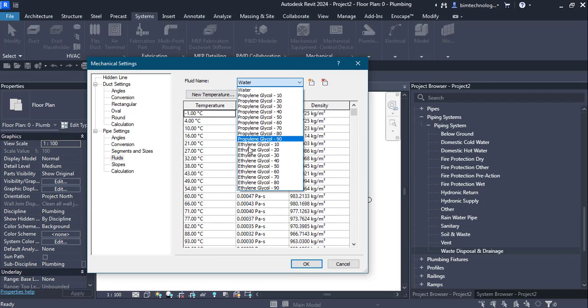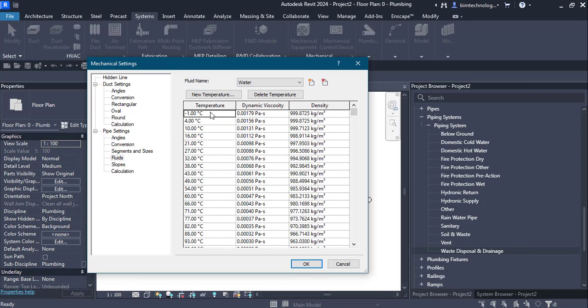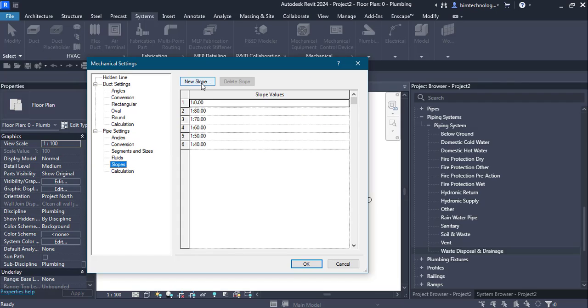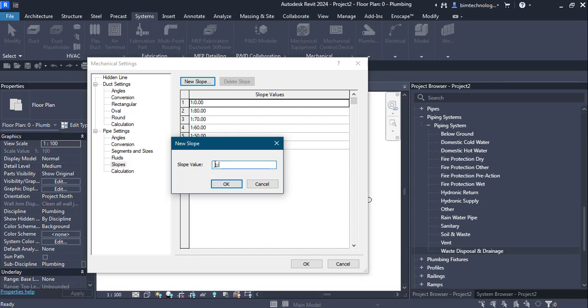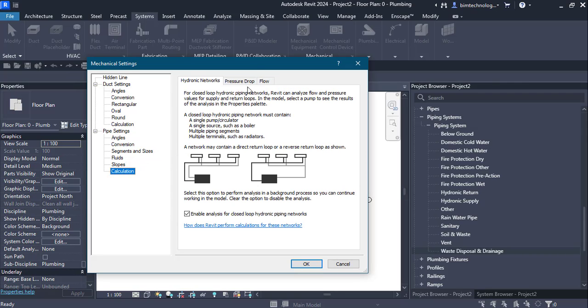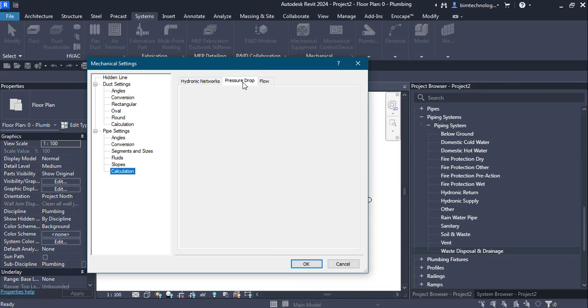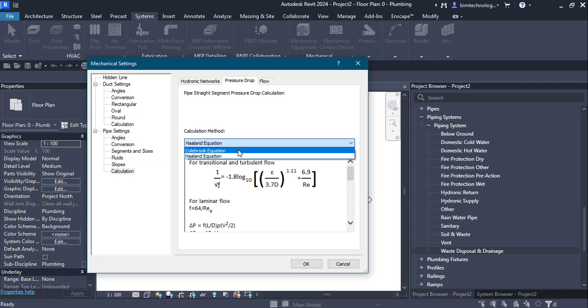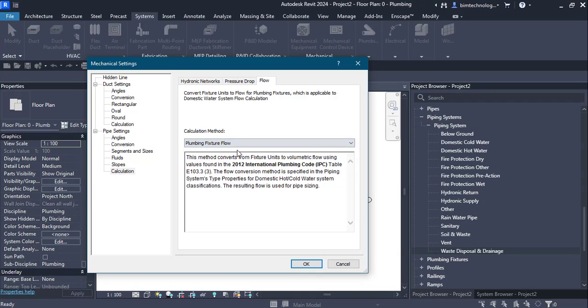Under fluids, you can define different types of fluids for the pipe, defined by temperature, dynamic viscosity, and density. You can create a new temperature chart or delete existing temperatures as needed. Slopes can also be defined — for example, adding a slope of 1 to 10. Finally, under calculations you have options for hydronic network pressure drop using the Colebrook or Haaland equation, and the flow calculation method according to the 2012 IPC table.